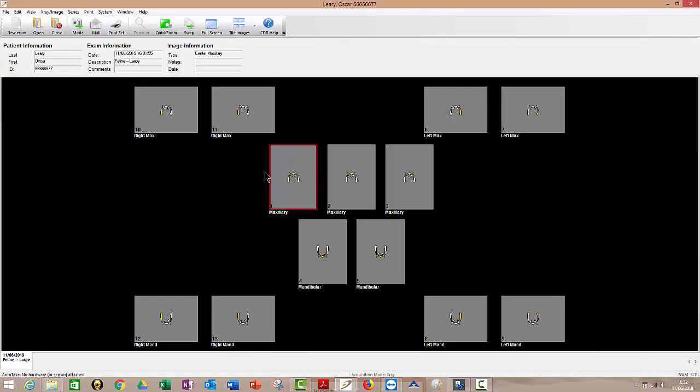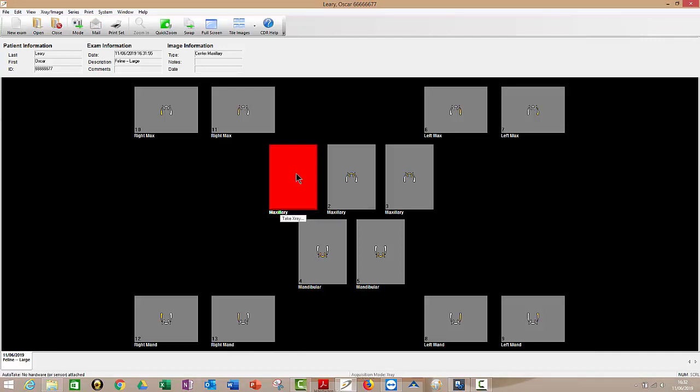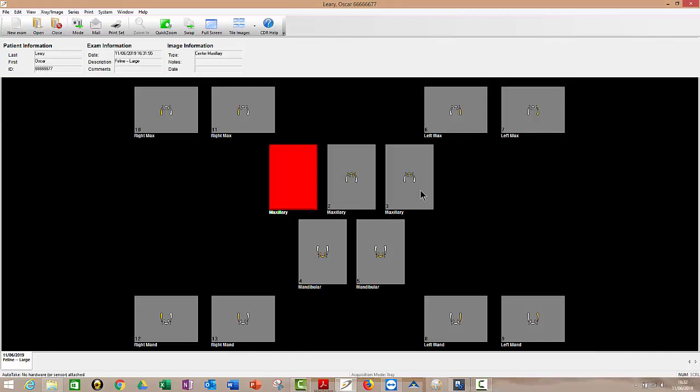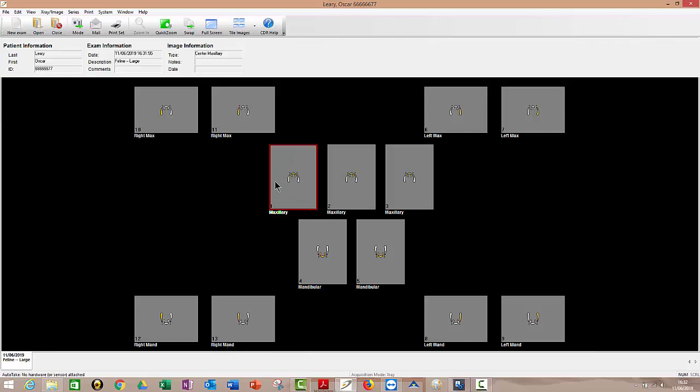I have a flashing red box here because I don't have a sensor attached. But if you had a sensor attached now, you'd see a flashing green box there. Now, if you notice, these boxes are numbered sequentially one, two, three, all the way up to how many is it? I think it's 13 by the look of it. So it's expecting me to put the sensor in the animal's mouth, fire my X-ray source at it, and my image will appear in this box here.